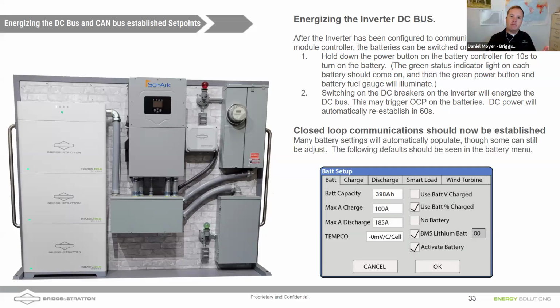Inverter's on, battery's on, and you start to drain the battery with no solar and no generator. The battery keeps draining. At some point the Sol-Ark gives off an alarm, and at some point it turns off the AC loads. If that happens, the Sol-Ark still has a parasitic draw—you still need to feed it some power to keep it alive so if the solar comes back, it can process and charge the battery. But if the Sol-Ark stays on and keeps draining the battery with that parasitic load, the battery will go into self-protect mode.